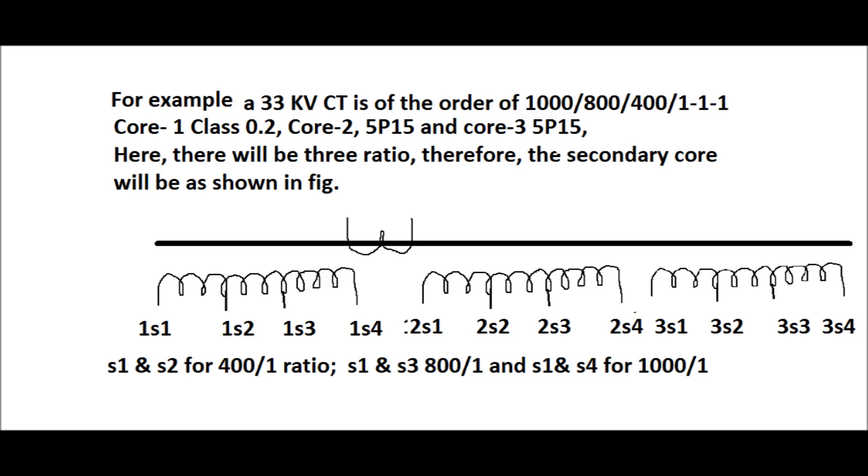Core 2 and 3 are used for protection purpose. Here there will be 3 ratios. Therefore, the secondary core will be shown in this figure. There will be 4 terminals in the secondary core. S1 and S2 will be taken for 400 by 1 ratio as the number of turns in the secondary is lower. And S1 and S3 are for 800 by 1 ratio. And S1 and S4 is used for highest ratio 1000 by 1 ampere.